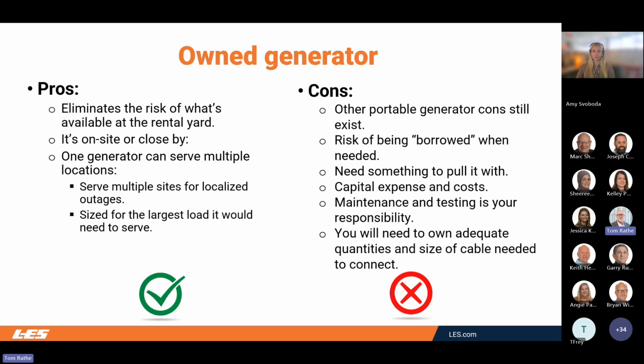So another option to that is owning a portable generator. Again, you have a lot of the other cons, but it might be a better solution in some cases. The pros of this: it eliminates the risk of what's available at the rental yard, and it's on site and close by, so potentially less time to get it into place and your critical load can be online faster. You could also have one portable generator that serves multiple satellite locations—set them up for the portable generator connection and dispatch a generator where it's needed.